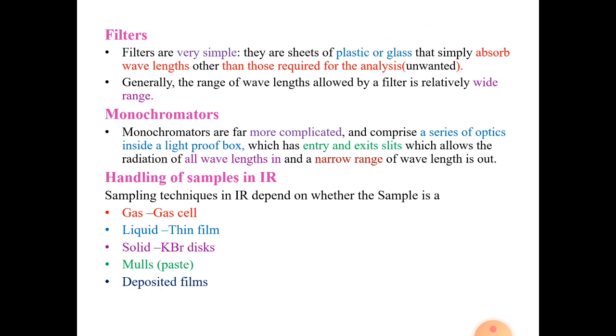The next one is filters. Filters are very simple. They are sheets of plastic or glass that simply absorb wavelengths other than those required for analysis. That is, unwanted wavelengths are absorbed and other wavelengths are sent to the sample. Generally, the range of wavelength allowed by the filter is relatively wide.